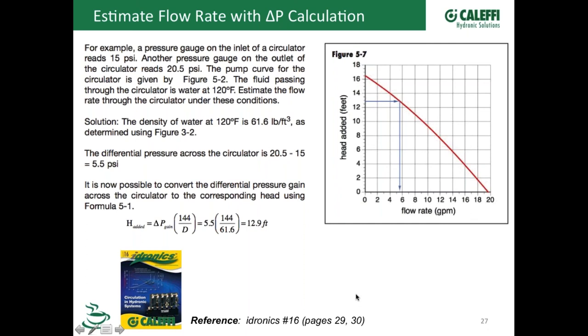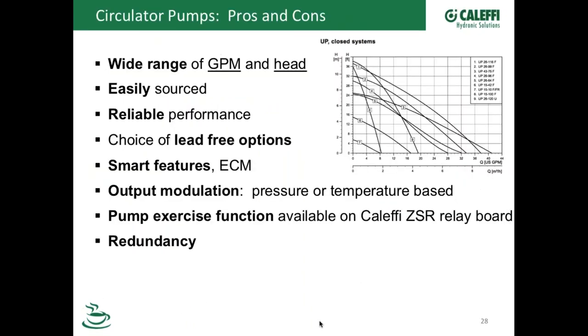There are differential pressure meters made that you can buy that will do that for you, with a single meter that can read both sides, or again, you can just get a good accurate gauge and do it yourself. Again, on pumps, I talked a little bit about the choices. Here's an example. You can see there are steep curve pumps that you might use for high flow resistance jobs, maybe thermostatic radiator valves or something like that. Those might be better with a high head circulator, and some of them have fairly flat curves, but there's pretty much a pump for everything.